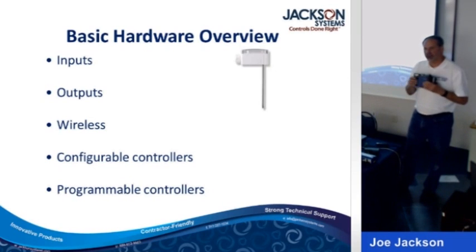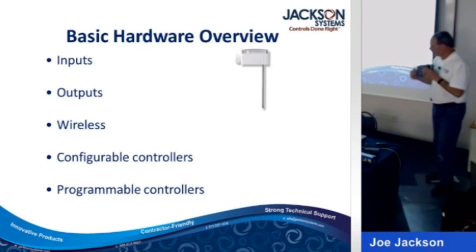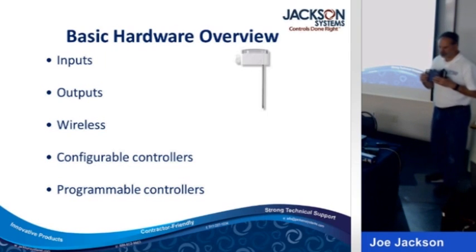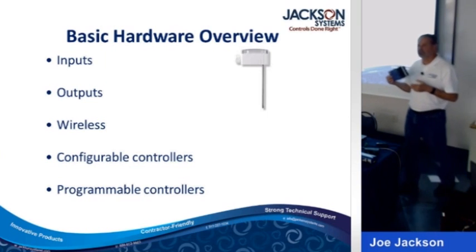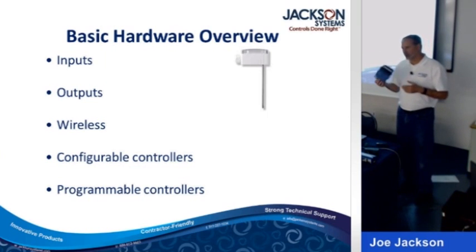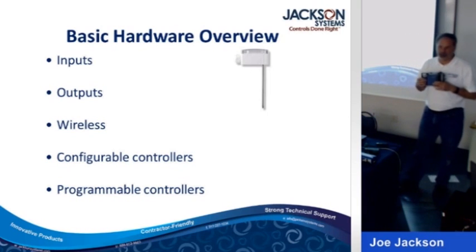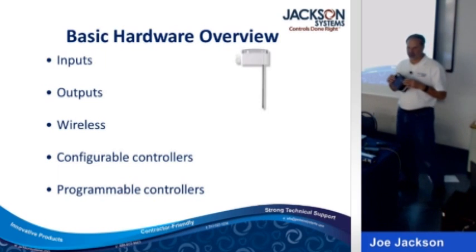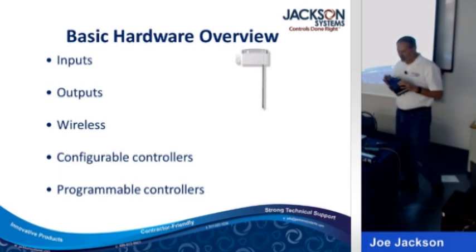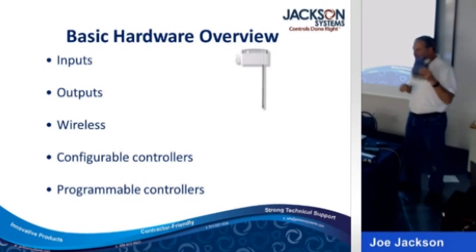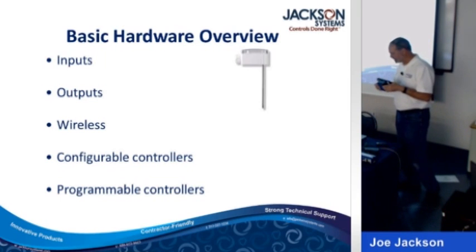But we talked about using a programmable version, one of these, so that we could vary the speed of a fan in a VAV box. Just not something you normally do. And ultimately, they decided not to do it because while it wasn't a real big deal to switch over to programmable controllers, it was a really big deal to put variable speed fans inside of VAV boxes that were already installed. So if you do have something special, VAV boxes can be either configurable or programmable.